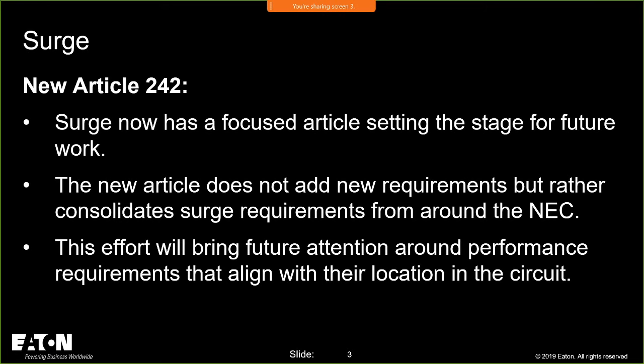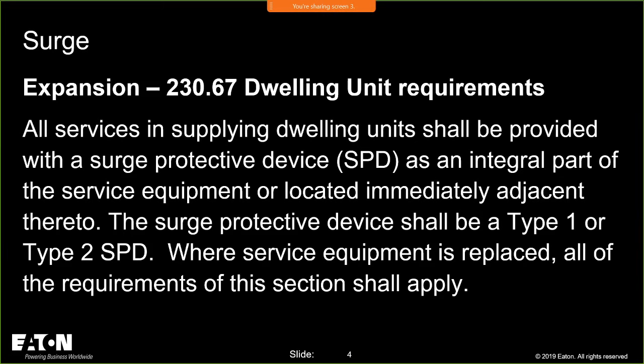In 230.67, it says all services supplying dwelling units have to be provided with a surge protective device, as an integral part of the service equipment or located immediately adjacent thereto. The immediately adjacent thereto is critical, because that lead length: the shorter the better, the longer the worse, if that's a word. You can take a very expensive surge device, put 6 foot or 12 foot of lead length on it, and it'll do nothing for you. So there's a lot to be learned about lead length.